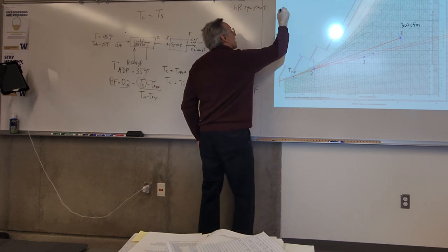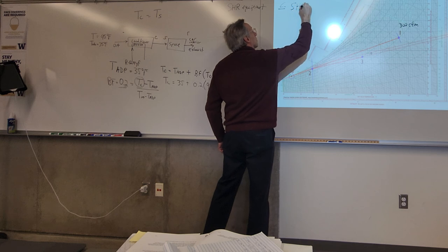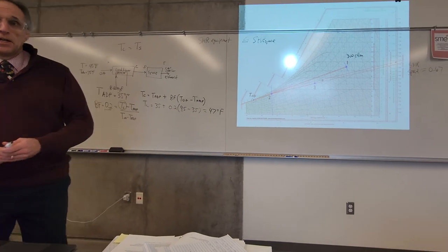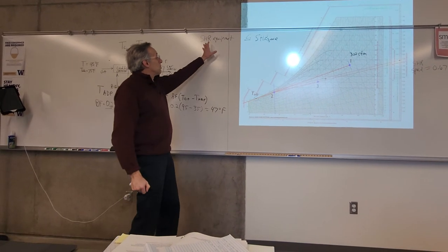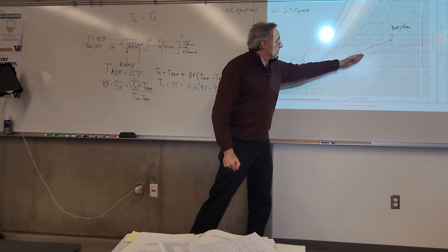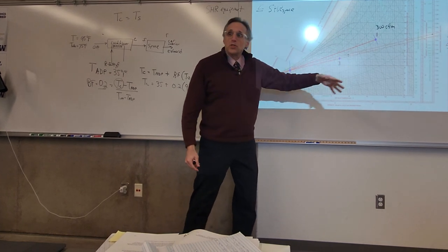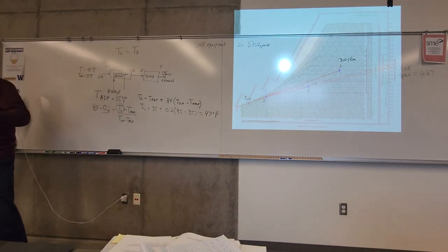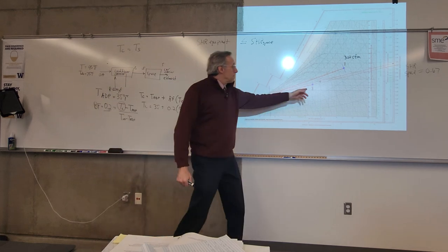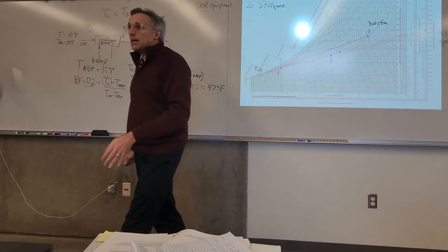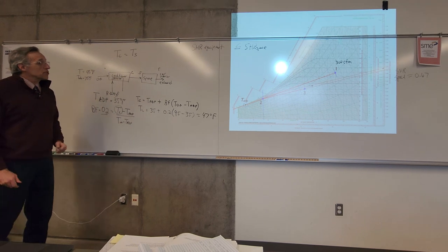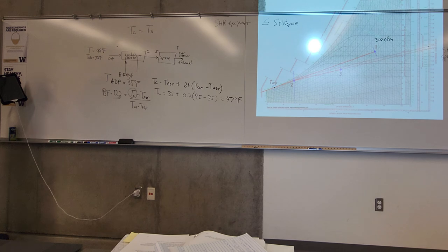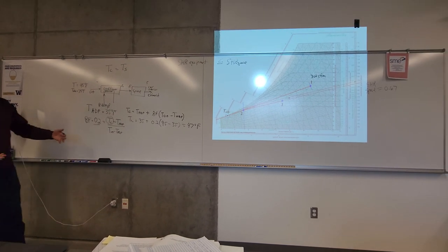This must be less than or equal to the space ratio at all times. It could be less than. You don't want this number to be greater than the sensible heat ratio for the space. When that happens, you can't dehumidify. Your air is going to be more humid than what your design state would be. But as long as you're at or below the space sensible heat ratio, the equipment should work if the control systems are properly designed. So, what is the sensible heat ratio of our equipment?